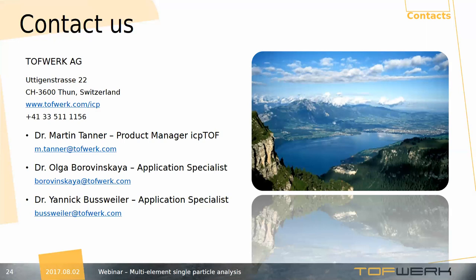Another question: is it possible to measure sulfur? Yes, it is always possible to measure sulfur. The main problem with sulfur is that there is a very intense oxygen peak next to it, and there is also a certain level of contamination of sulfur in water. Up to now we could show detection limits of about 10 ppb, which is not very low, but we are working on it and are in the process of investigating the capabilities of ICP-TOF-2R specifically for sulfur detection.